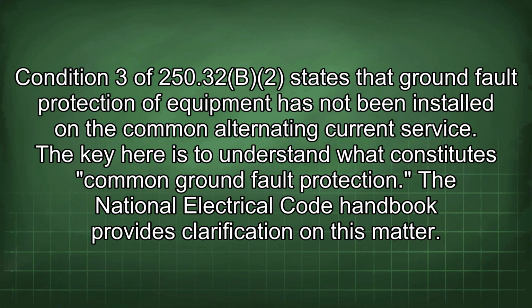Condition 3 of 250.32(B)(2) states that ground fault protection of equipment has not been installed on the common alternating current service. The key here is to understand what constitutes common ground fault protection. The National Electrical Code Handbook provides clarification on this matter.